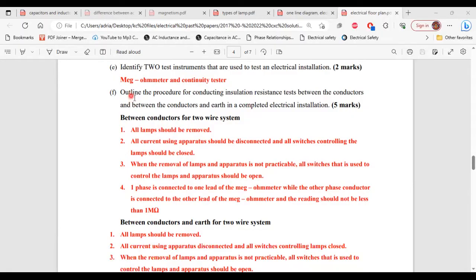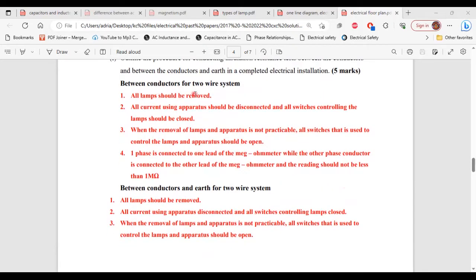For Part F, outline the procedure for conducting insulation resistance tests between the conductors in a two-wire system. 1 — all lamps should be removed. 2 — all current-using apparatus should be disconnected and all switches controlling the lamps should be closed. 3 — when the removal of lamps and apparatus is not practicable, all switches used to control the lamps and apparatus should be open. 4 — one phase conductor is connected to one lead of the megohm meter while the other phase conductor is connected to the other lead; the reading should not be less than one megohm.